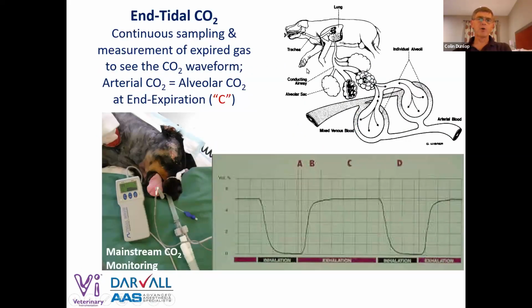So in order for capnography to work, we've got to have an animal. So this dog breathes. We can see that the CO2 is down here in the alveoli. That CO2's got to come up to the point where we're going to sample it, which is the endotracheal tube connection. So you can see that the length of tubing coming down to the lung, the trachea and airways, when the dog breathes in at the end of inspiration, that has room air in it. So when the dog breathes out, that gas comes out first. That's what's called the anatomic or the physiologic dead space.